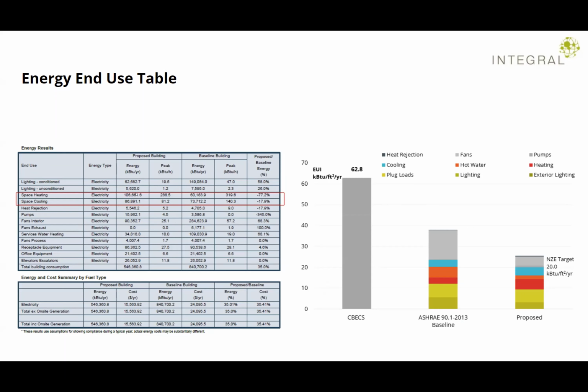Again, this is a building based in Atlanta. It's 20,000 square feet. So what if this was reversed? What if heating was... it shows here that heating is higher than cooling, for example. So this is something that I would definitely check as to why heating is higher than cooling in Atlanta. So there are some basic checks that you would do just based on the climate zone that you're modeling.